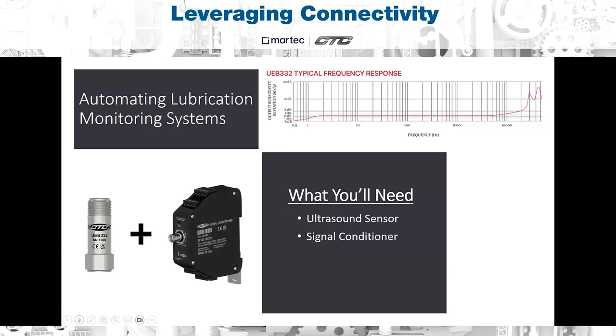So when paired with the SC320 signal conditioner, it allows you to get a dual 4 to 20 milliamp output from 2 separate frequency bands of one sensor. So kind of how that works is with a UEB sensor, you can configure the first 4 to 20 milliamp output to the typical vibration levels from 1 hertz to 1,000 hertz, for example. This frequency band will be used to monitor typical bearing defects. The second 4 to 20 milliamp output can then be configured to the ultrasonic range from 23 kilohertz all the way up to 42 kilohertz, and that will be to monitor the lubrication.